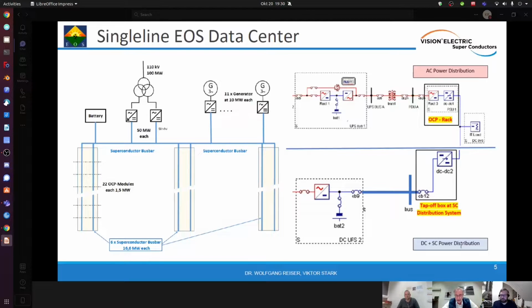That high efficiency is reached through a lot of redundancies, and redundancy in this case could also apply here. Of course, here we also show some redundancies. If the grid has a failure or a blackout, the generator units come up and supply power to the data center. High powers in this case also create high currents, and presently we are demonstrating a 200 kiloamp busbar system in an aluminum plant. So yes, it exists and it's working well.